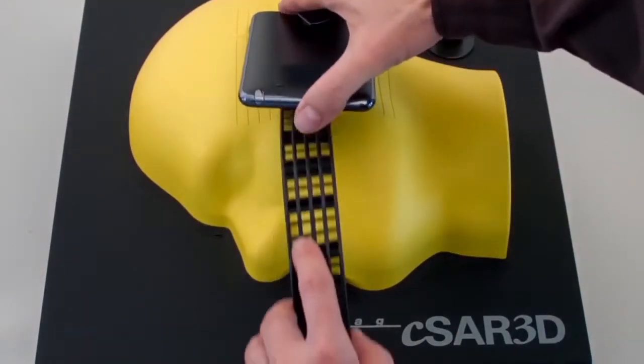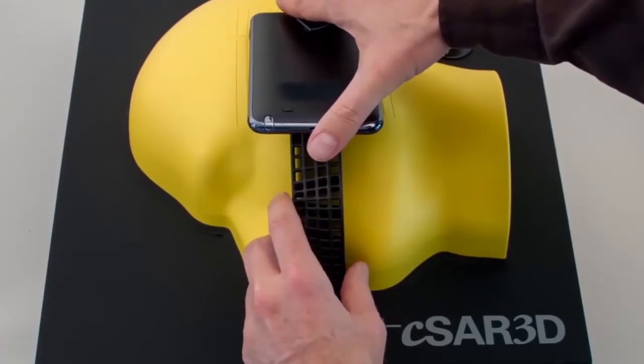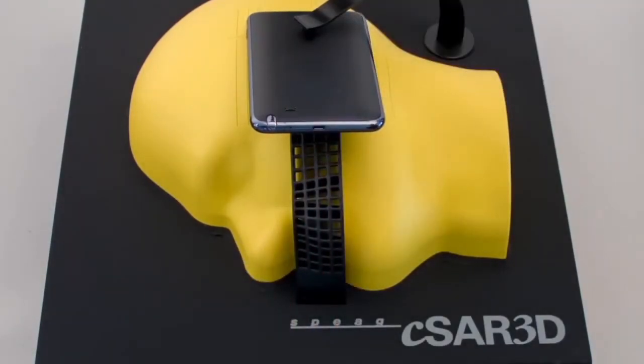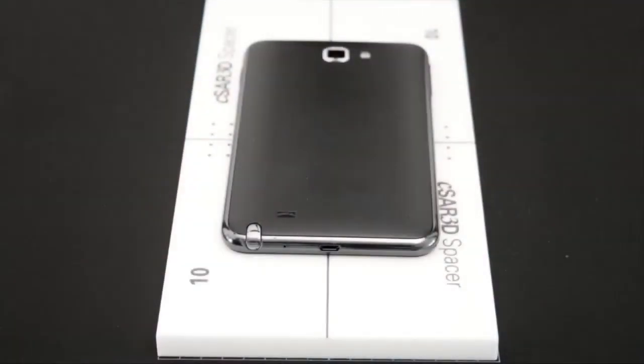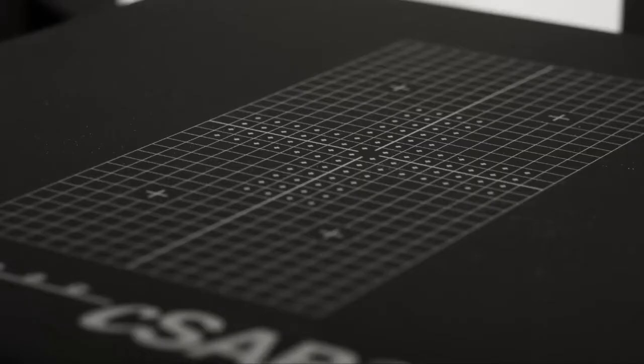The head phantoms also come with a low permittivity mask that aids in placing the device in the 15-degree tilt position. Flat phantoms are used for SAR testing during body-worn use, and they can be ordered with either body-simulating or head-simulating dielectric media. Both media have been formulated at SPEAG and match the permittivity targets over a broad frequency range. The measurement area of the flat phantom is suitable for smartphones and some tablets. For larger devices, including laptops, the cSAR3D Quad is available.